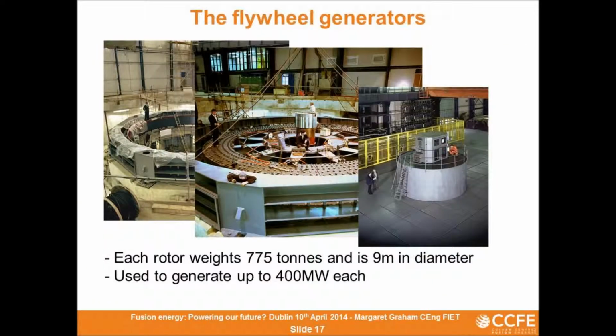So, flywheel generators — these are impressive, I'm very impressed with this. The engineering that goes into this is fantastic. We've had problems where they've had to level it due to vibrations, which couldn't be allowed, especially given the weight, and the fact that they rotate at 225 revs per minute for about 10 minutes before the pulse actually goes.